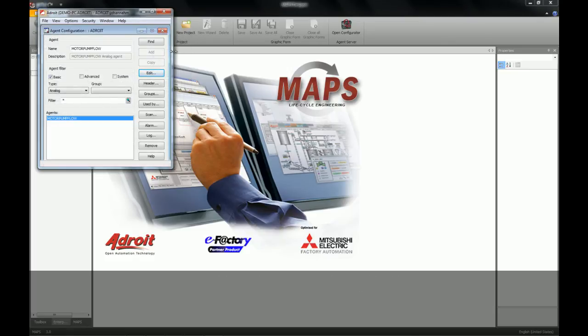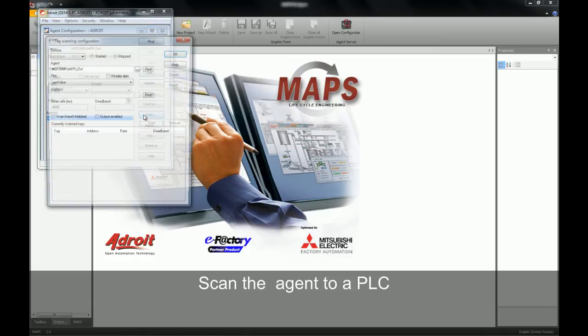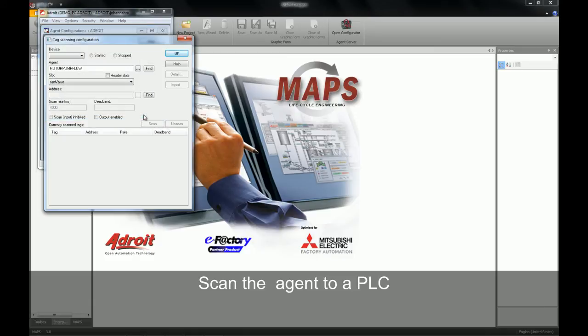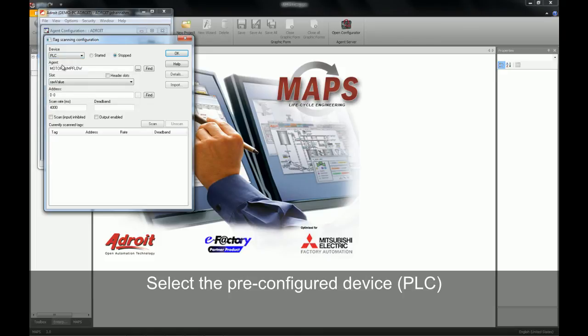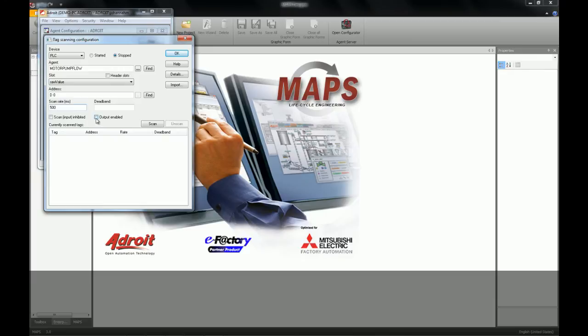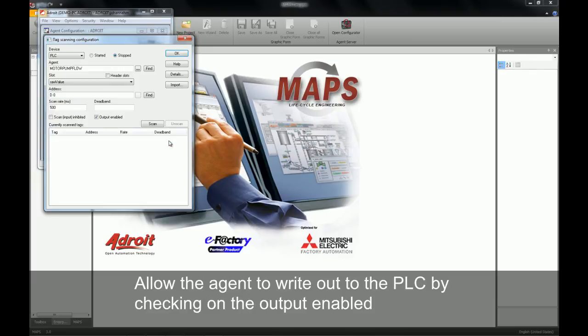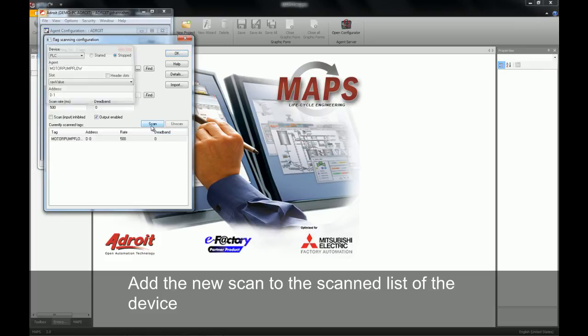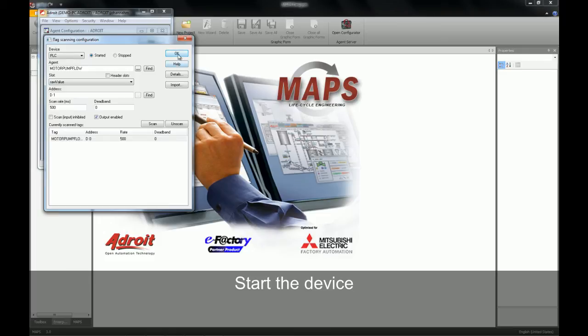We can now go and attach this to a PLC's registry. To do this, click on the scan button which will open up our scanning dialog. We then select the device — in our case it'll be the PLC device which we configured in a previous exercise. I'm going to leave my address as the default and change my scan rate to 500 milliseconds. By checking the output enabled checkbox, I will enable this agent to write out to the PLC. We then scan it and start our device, and click OK.